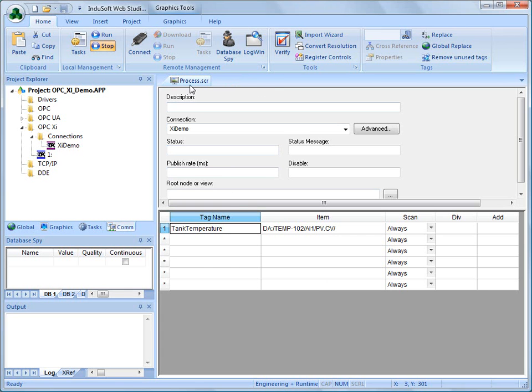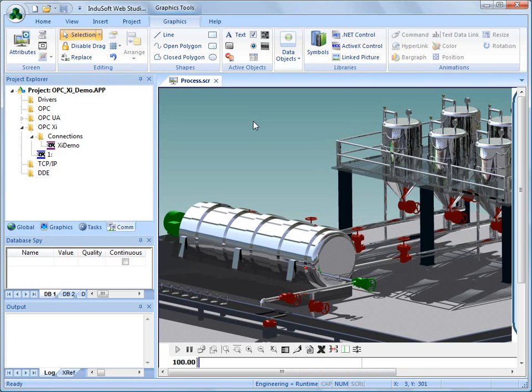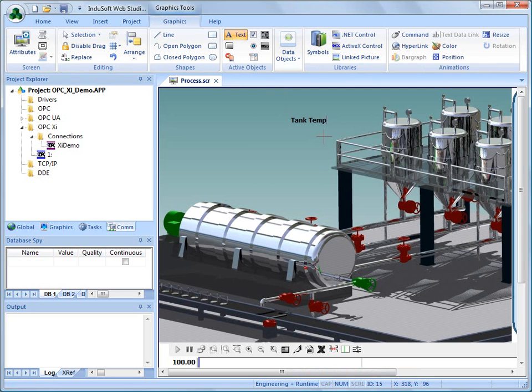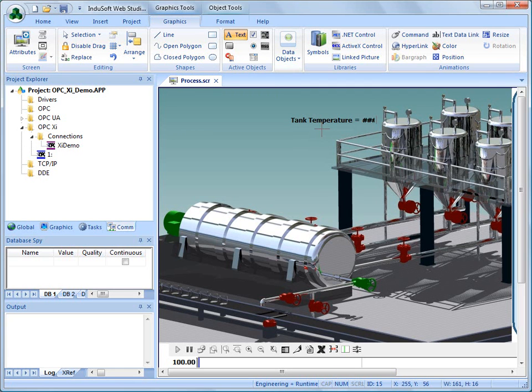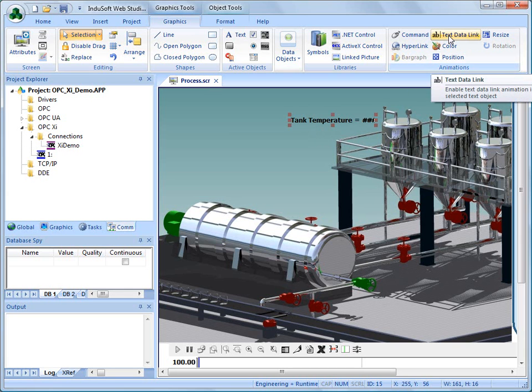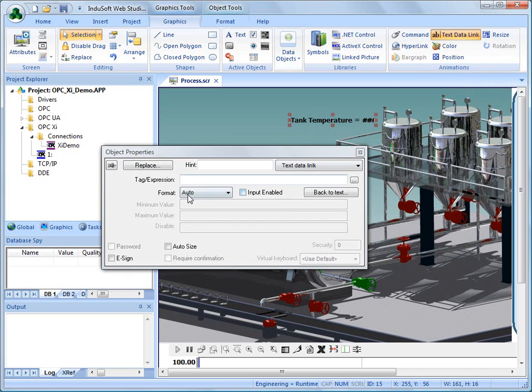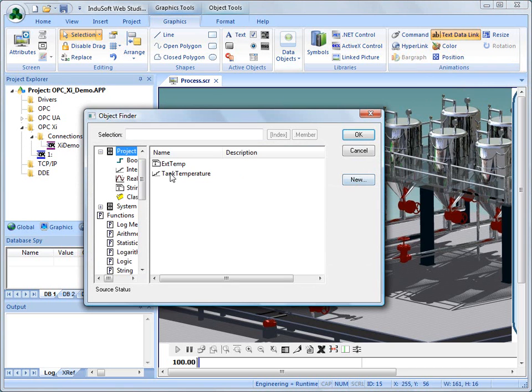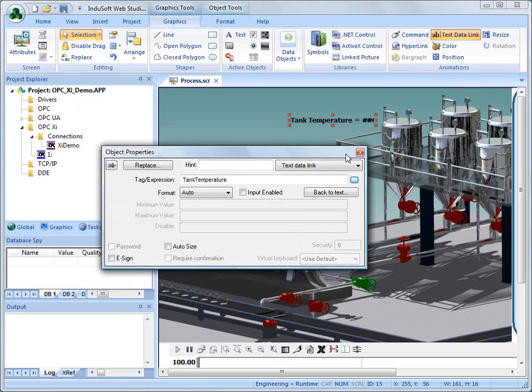So, now that I have this established, I'm going to go back to my screen, and I'm going to add a piece of data. Let's say this is the tank temperature for this tank here. I'm going to add some text here that says tank temperature, and I'm going to add some pound signs after this. Now, the pound signs are a little special in Indusoft Web Studio. They allow me to get data in or out using this animation here called the text data link. So, now I can tie that piece of text to the tag that we just created called tank temperature.